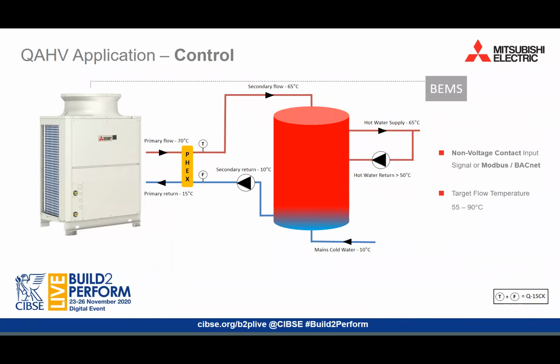An alternative control method is to simply operate the unit with a target flow temperature, actioned by an external signal. This signal could be a non-voltage contact directly connected to the unit's board, or via a BEMS input over Modbus or BACnet. And again, for example, the temperature in the vessel here could be monitored by the BMS and trigger a signal when a particular condition is met, which then enables the QAHV to run at its predefined and commissioned target flow temperature. That flow temperature could be anywhere between 55 and 90 degrees Celsius, and return off when the signal is stopped.